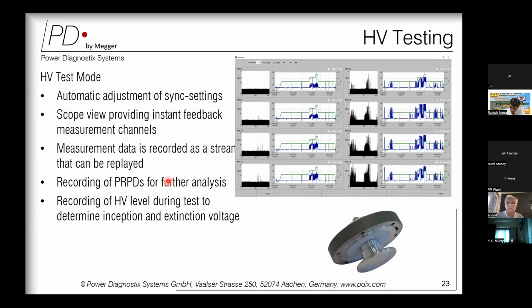partial discharge measurement. Now, whenever we do HV test mode, generally the instrument is parallelly connected on all the channels and the recording should be performed, where an instantaneous PD is recorded into the scope mode, and then the data is recorded in form of PD and the high voltage, because as we talked earlier, some synchronization is required with the high voltage, and the same data our instrument can also record. So as we see in all this parallel measurement window, we have a scope mode where instantaneous PD value is measured. We have a recorder mode where PD value and the high voltage are recorded over a period of time. They are recorded as a stream.